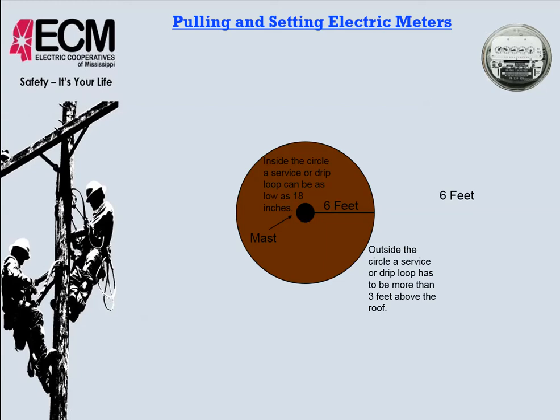So 6 feet away from this pipe, it has to be at least 18 inches. It can be as low as 18 inches between it and the roof. Okay, outside of the 6 foot radius, it has to be 3 feet, depending on the angle in which it runs in. So that's just something to be mindful of. That is a meter base that we could not set a meter on if it didn't meet that requirement.